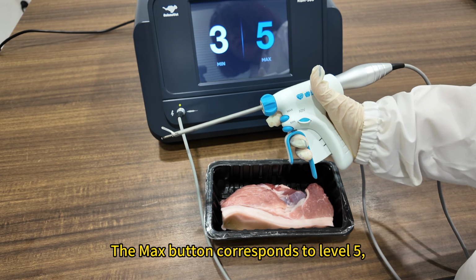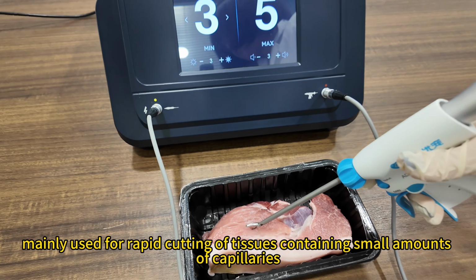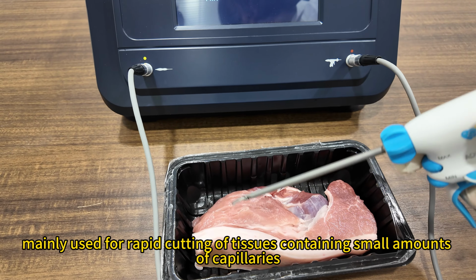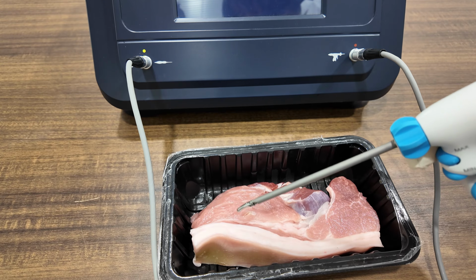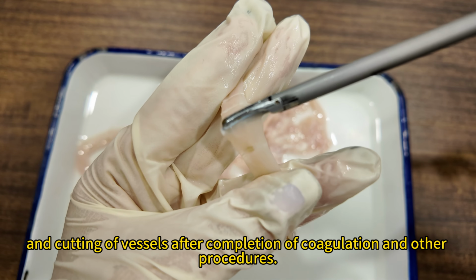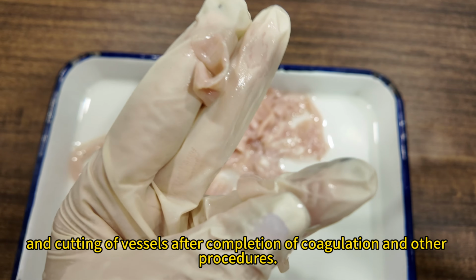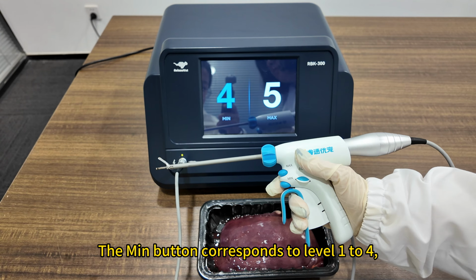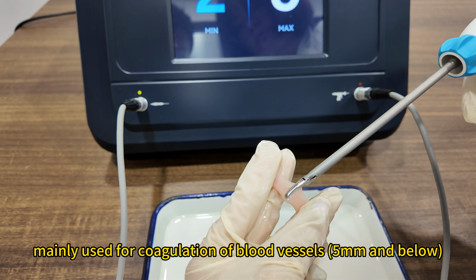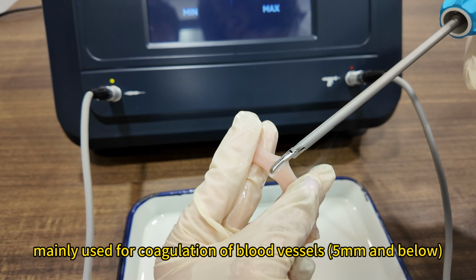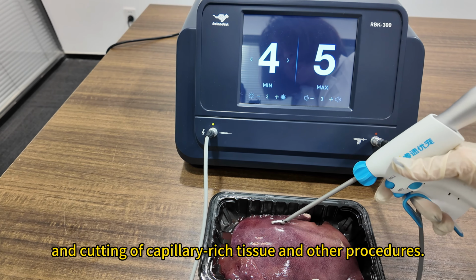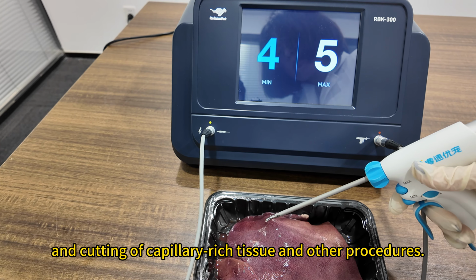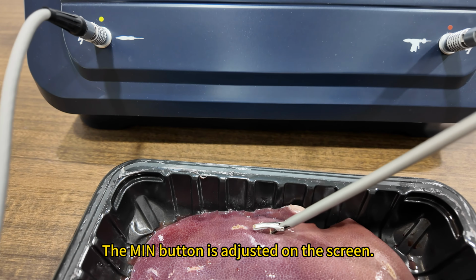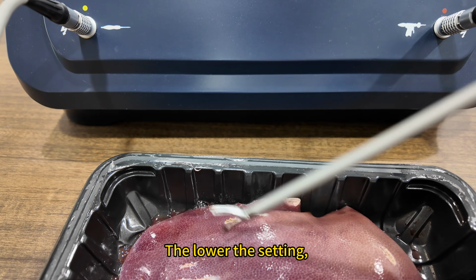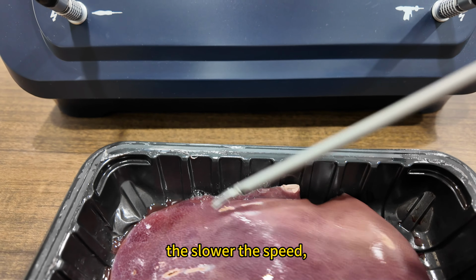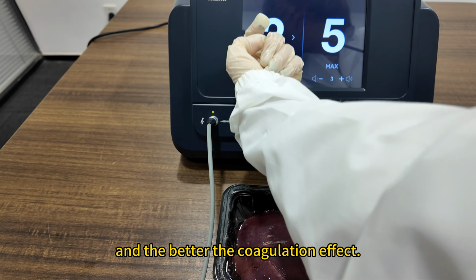The max button corresponds to level 5. Mainly used for rapid cutting of tissues containing small amounts of capillaries, and cutting of vessels after completion of coagulation and other procedures. The min button corresponds to levels 1 to 4, mainly used for coagulation of blood vessels 5 mm and below, and cutting of capillary-rich tissue and other procedures. The min button is adjusted on the screen. The lower the setting, the slower the speed, and the better the coagulation effect.